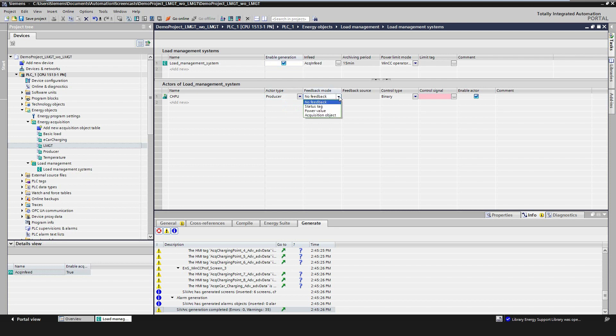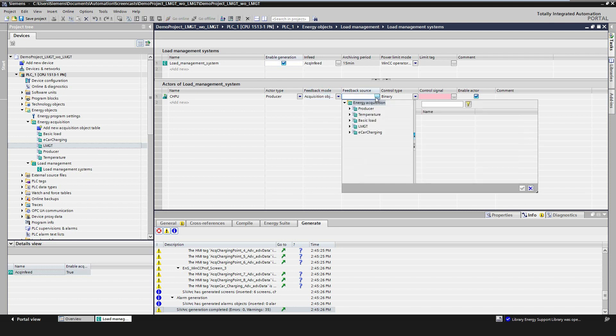There are four possibilities to get the feedback of the actor. First, a binary status signal, for example, the feedback signal from a switch. Second, an analog value, for example, the active power of a consumer or producer. Third, an acquisition object which has been created before. And fourth, or completely no feedback, which is not recommended as the system gets absolutely no information about the current status of the actor.